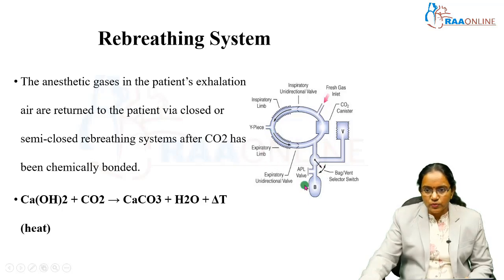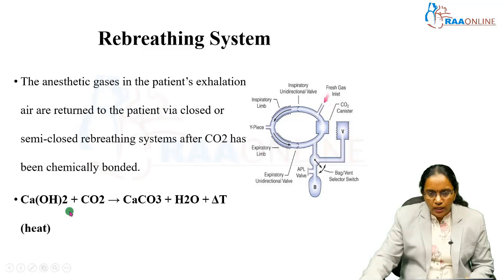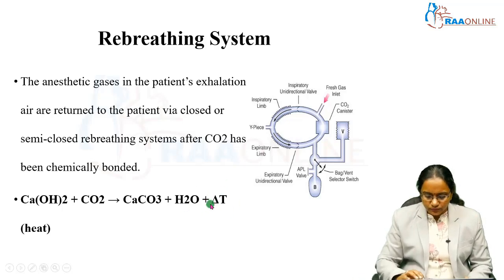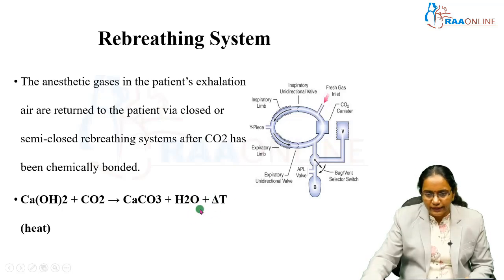This is a bag-ventilator switch, this is the bag assembly, and this is the ventilator assembly. What is most important in the re-breathing system is the chemical bonding of CO2 through the CO2 absorber. The classical equation is CaOH2 + CO2, which gives calcium carbonate plus water. This is an exothermic reaction which generates heat. This water and heat act as a heat-moisture exchanger so the air is not dried up.